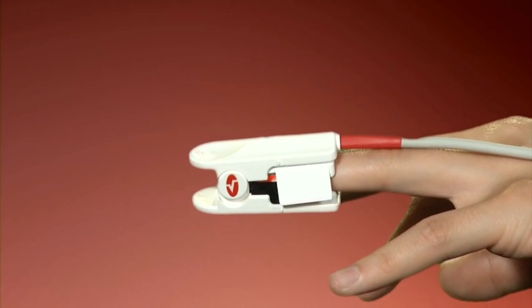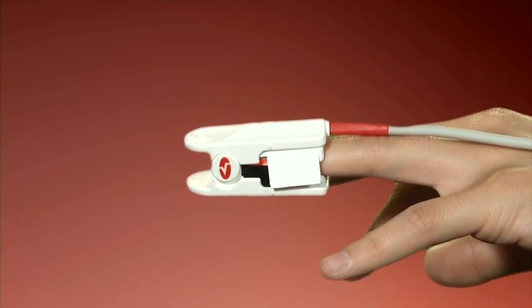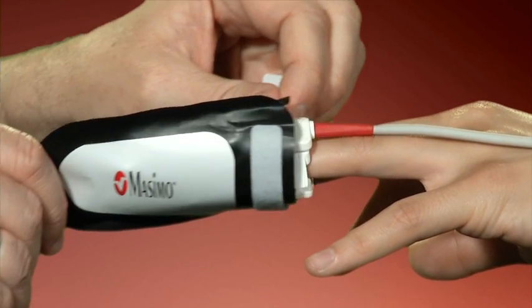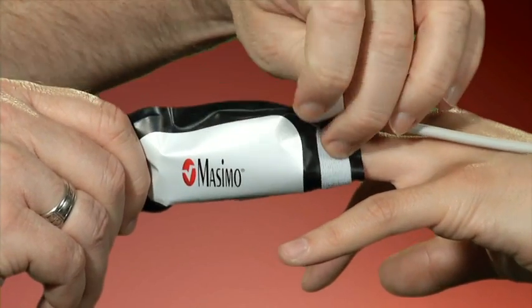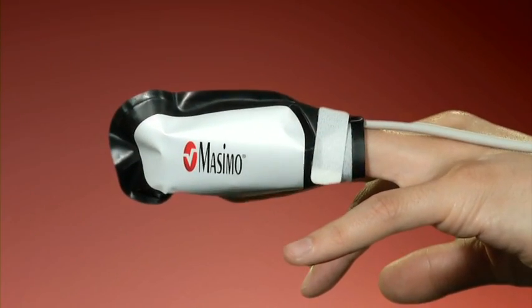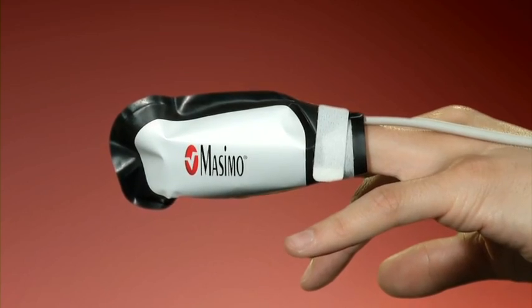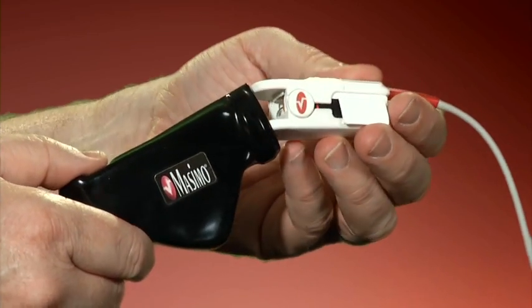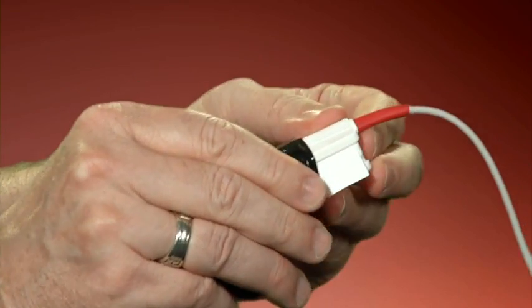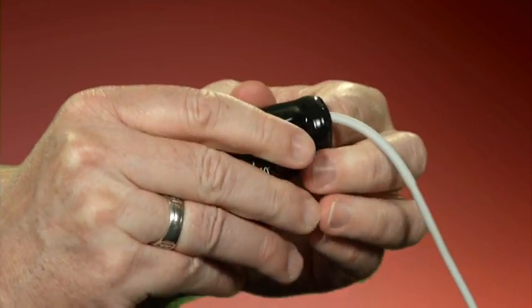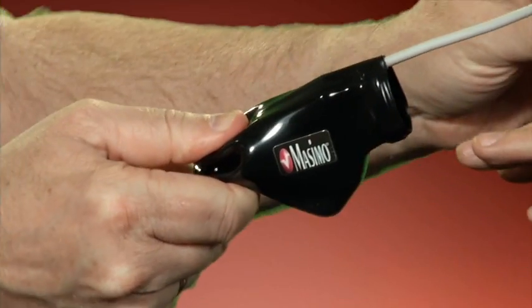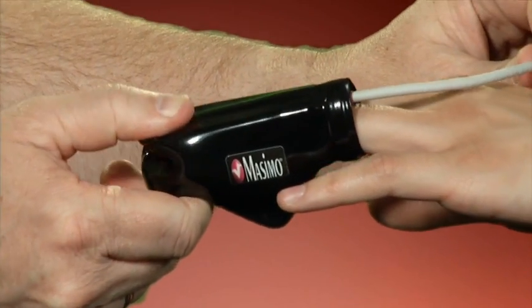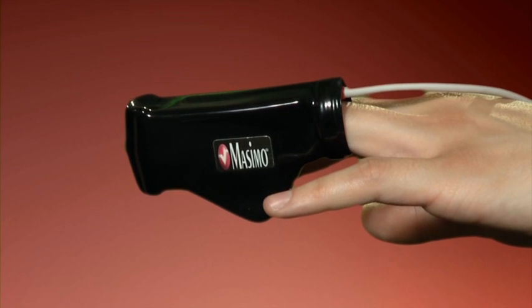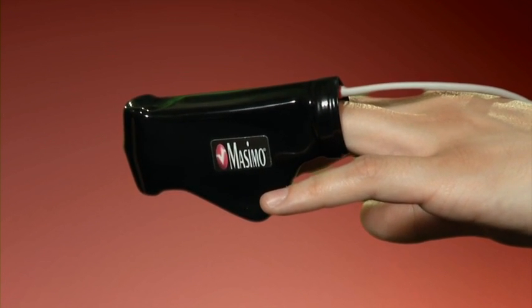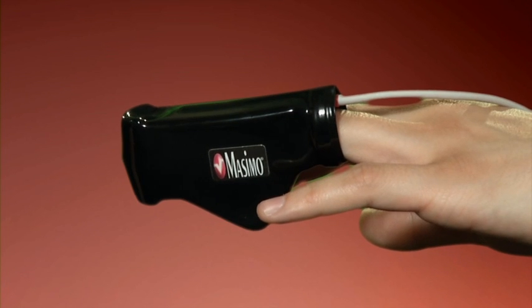If you are using the bag shield that came with your sensor, place the sensor on the patient's finger first. Then, place the bag over the sensor and secure it with the Velcro strap. If you've elected to use the rubber boot shield, insert the sensor all the way into the light shield prior to placing it on the patient's finger. The cable should run out of the top of the opening. Once the sensor is in the light shield, insert the finger into the sensor, making sure that it is properly aligned, and the finger is pushed all the way to the digit stop.